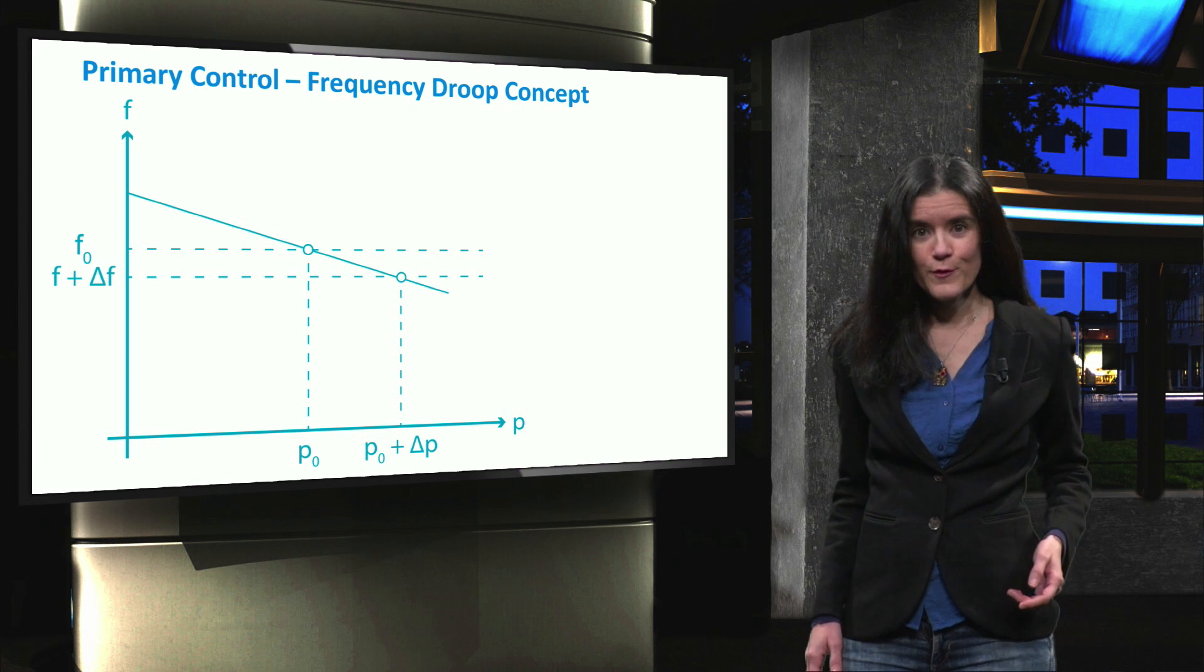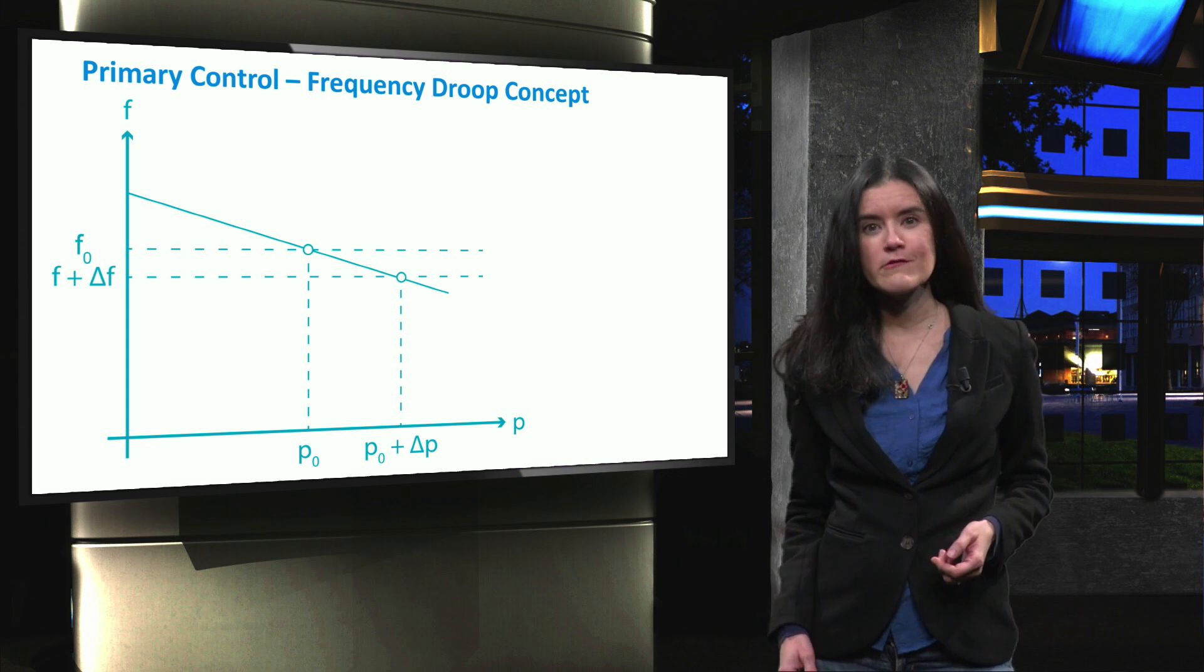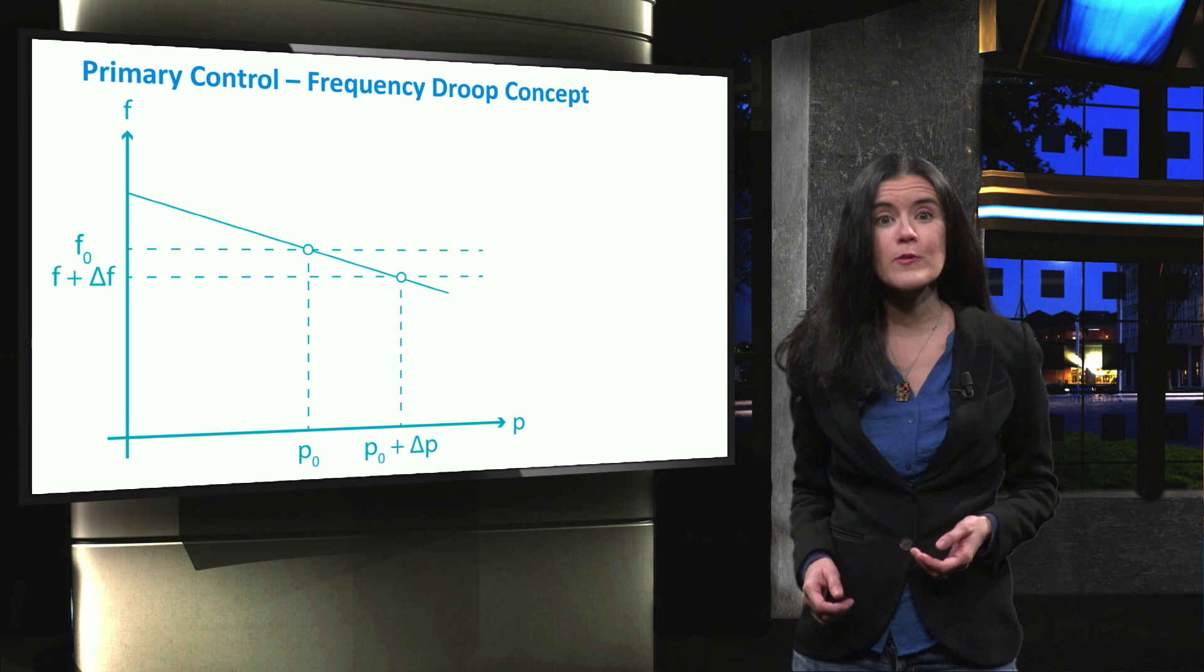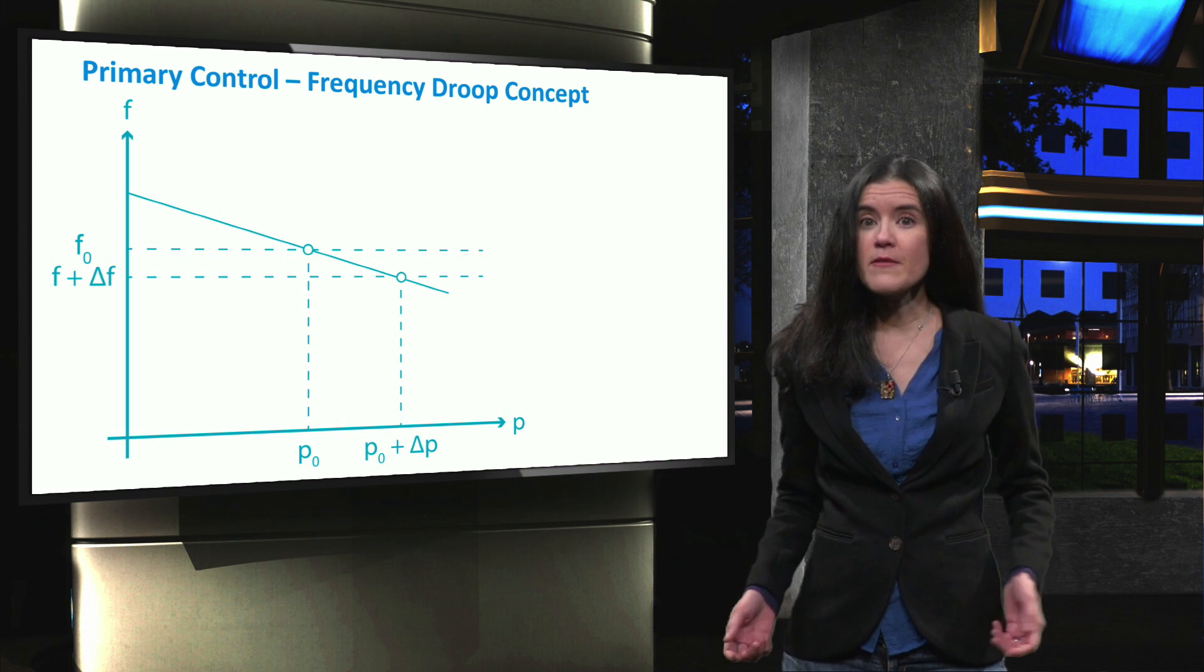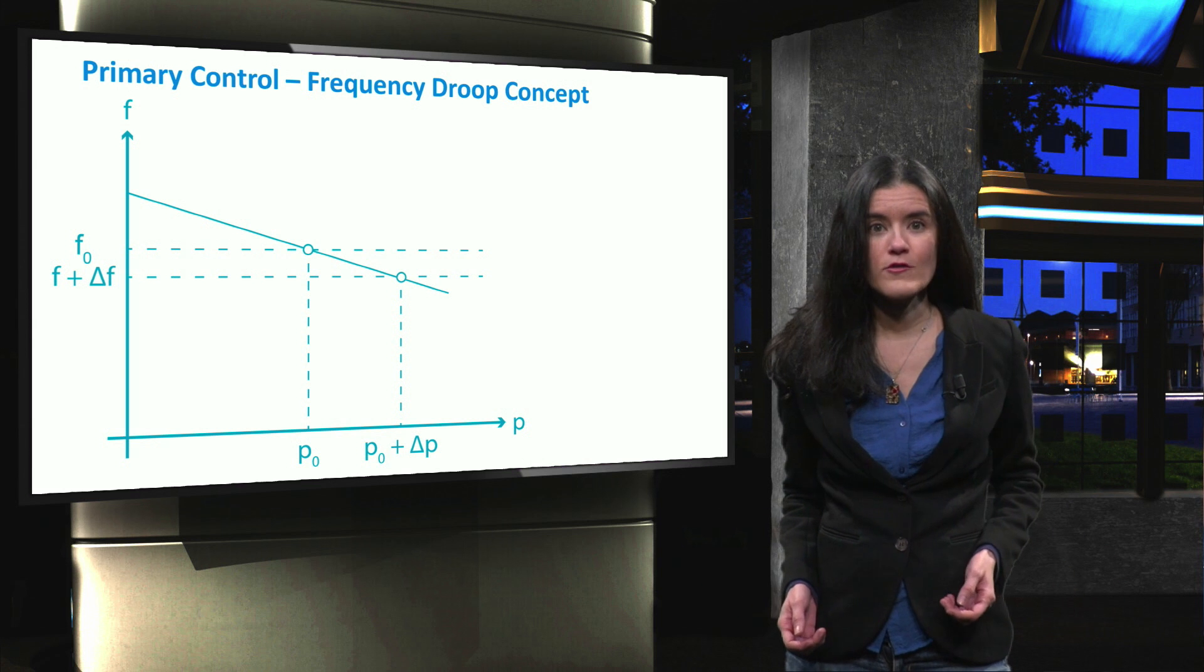The droop is the frequency drop in per unit of the rated frequency when the active power output of the generator rises from no load to full load. It can be mathematically described by the equation on your screen.